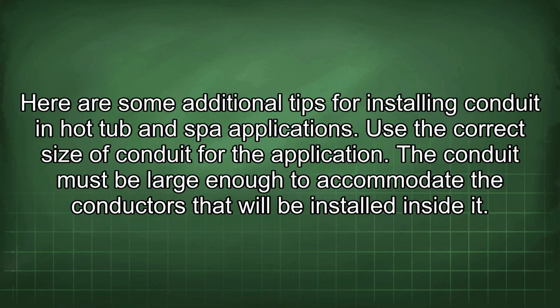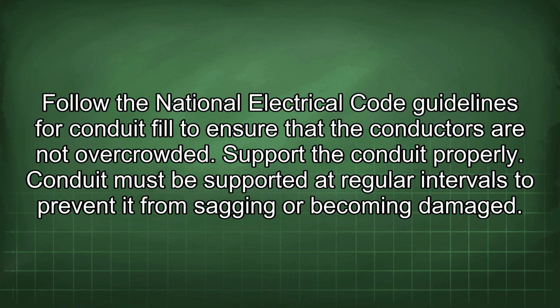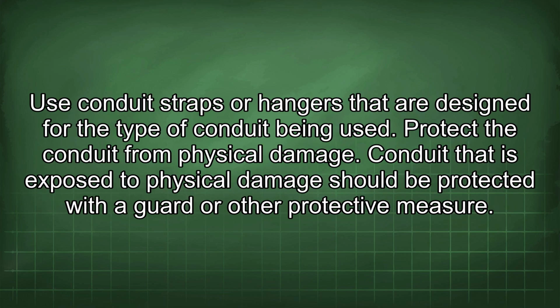Here are some additional tips for installing conduit in hot tub and spa applications. Use the correct size of conduit for the application. The conduit must be large enough to accommodate the conductors that will be installed inside it. Follow the National Electrical Code guidelines for conduit fill to ensure that the conductors are not overcrowded. Support the conduit properly. Conduit must be supported at regular intervals to prevent it from sagging or becoming damaged. Use conduit straps or hangers that are designed for the type of conduit being used. Protect the conduit from physical damage.